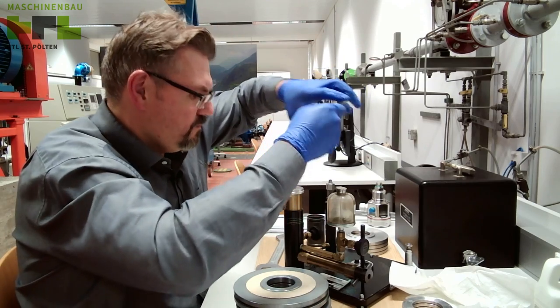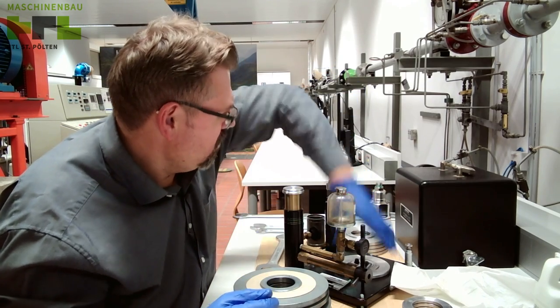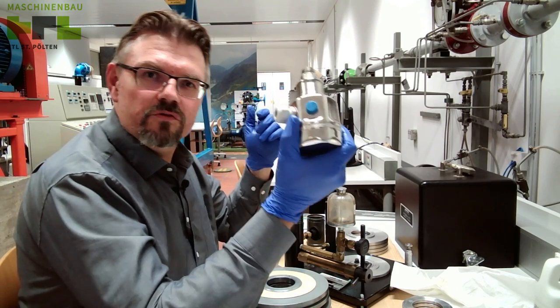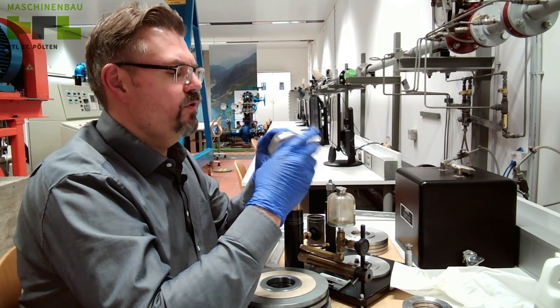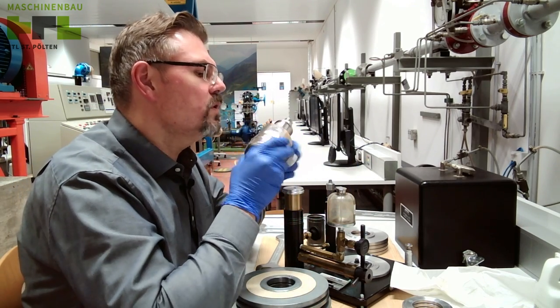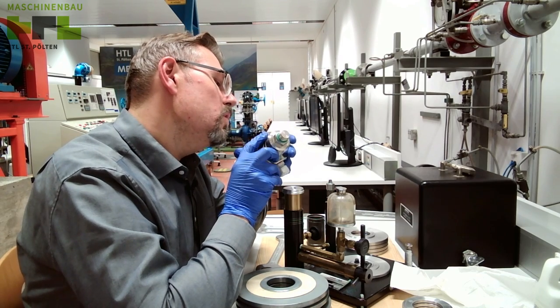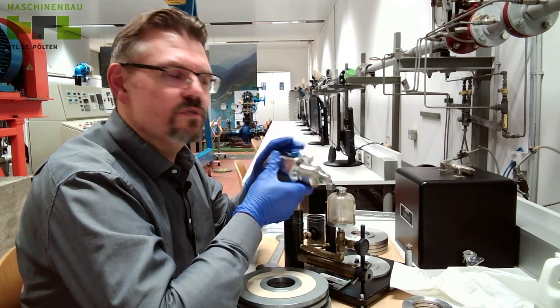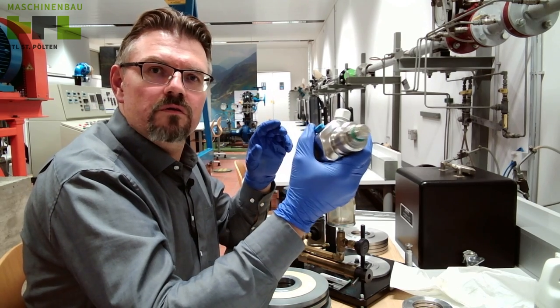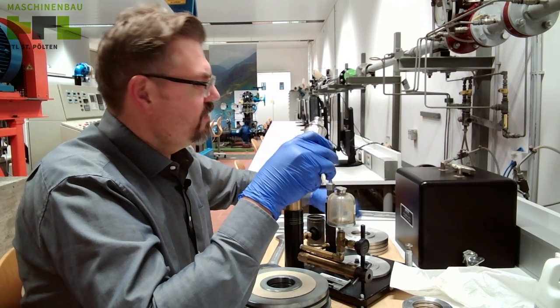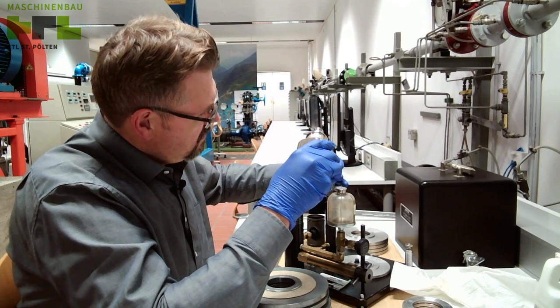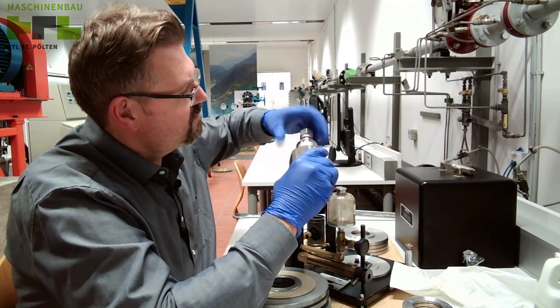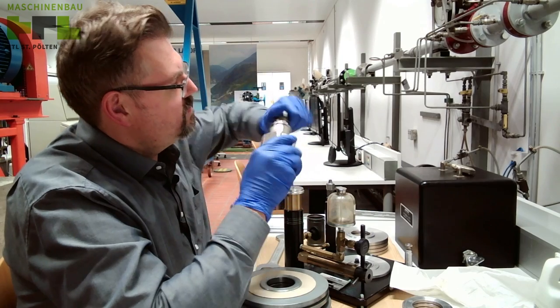So I am also going to mount here my pressure sensor, this is the device I want to test. This is a 0 to 10 bar, 4 to 20 milliamp pressure sensor. I am going to mount this. And this should fit, yes it fits. Let's mount this. It's also a 27, I think.